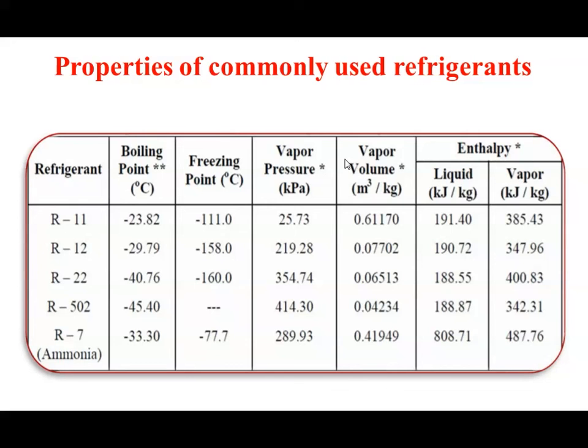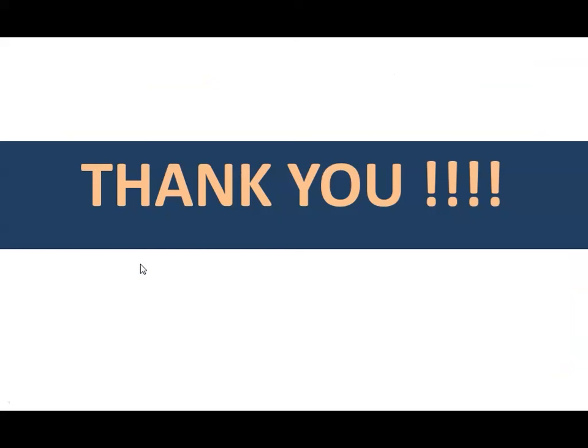Commonly used refrigerants in VCR systems include R11, R12, R22, R502, R717 (ammonia). Their boiling points are all negative — in negative temperature range. The table shows their properties: boiling point, freezing point (as low as -111 degrees centigrade), vapor pressure, vapor volume, and enthalpies. These are the properties of commonly used refrigerants in VCR systems. Thank you — that was all about today's topic.